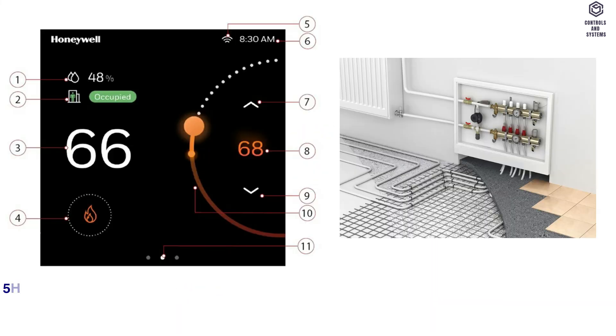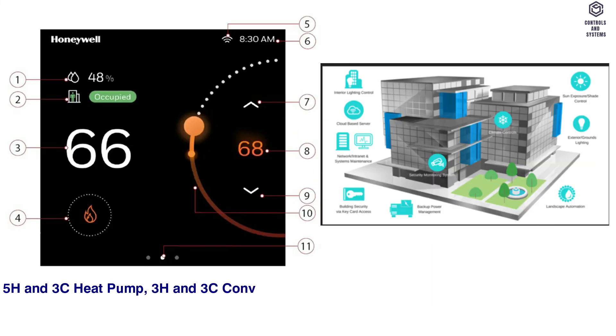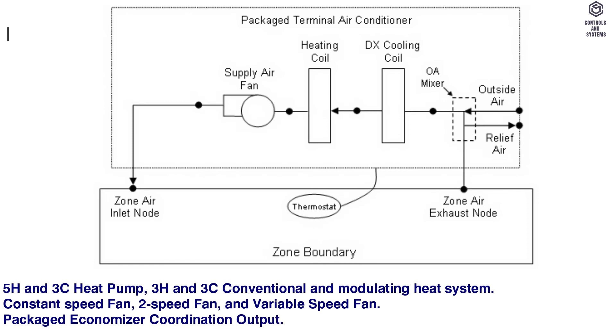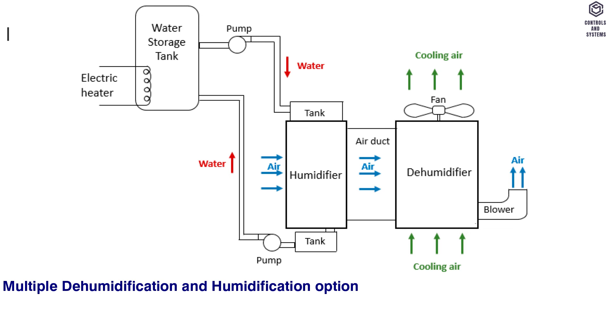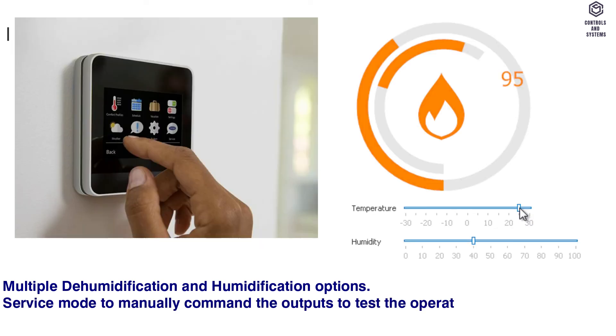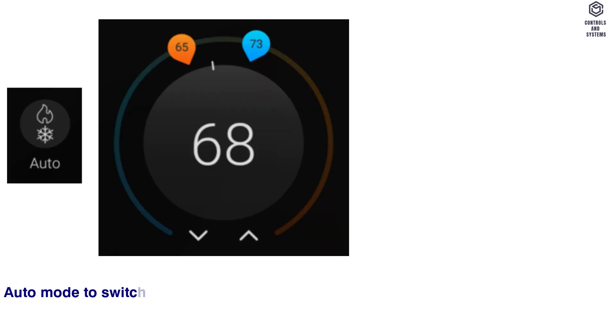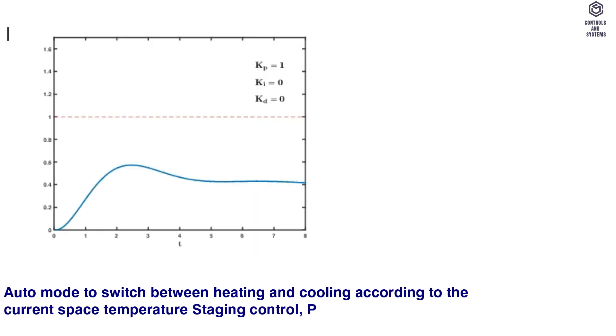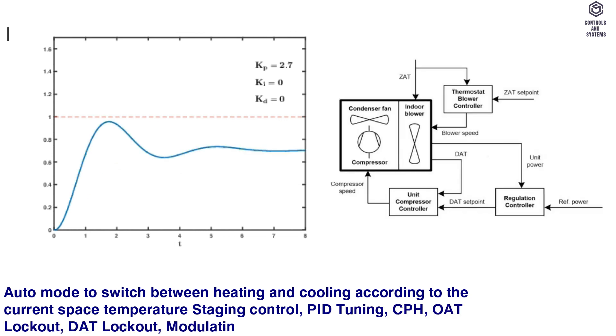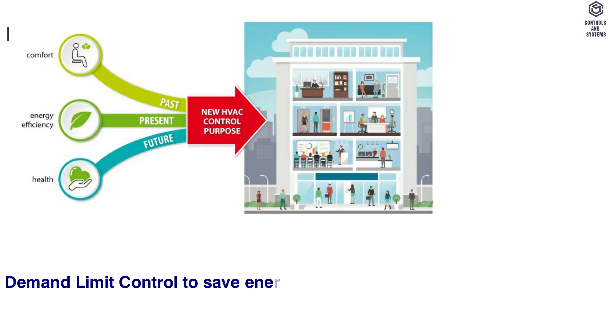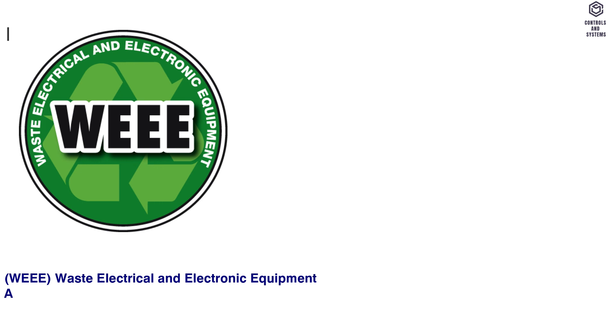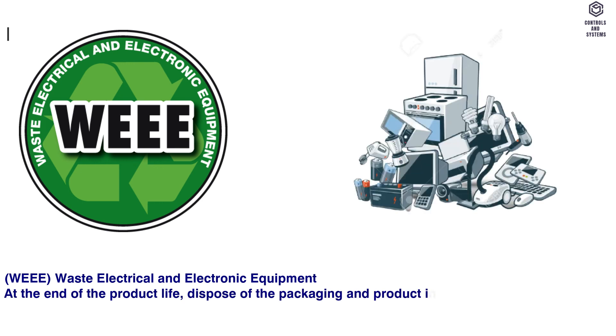Equipment control features: 5 heating and 3 cooling heat pump; 3 heating and 3 cooling conventional and modulating heat system. Constant speed fan, 2-speed fan, and variable speed fan. Packaged economizer coordination output. Multiple dehumidification and humidification options. Service mode to manually command outputs to test mechanical equipment. Auto mode to switch between heating and cooling according to current space temperature. Staging control, PID tuning, CPH, OAT lockout, DAT lockout, modulating control. Demand limit control to save energy. System switch options and smoke monitor. WEEE: at the end of product life, dispose of the packaging and product in an appropriate recycling center.